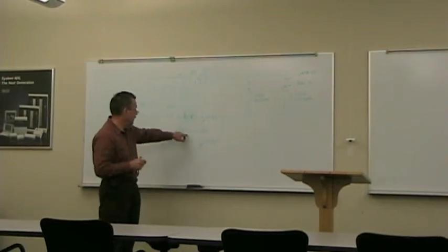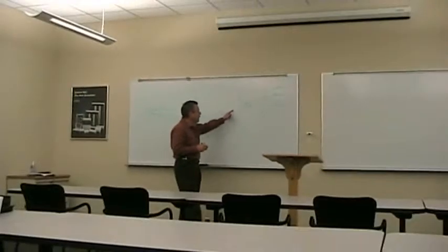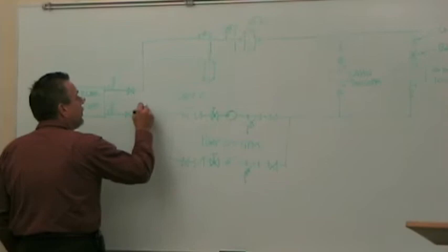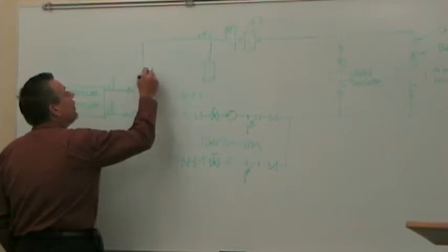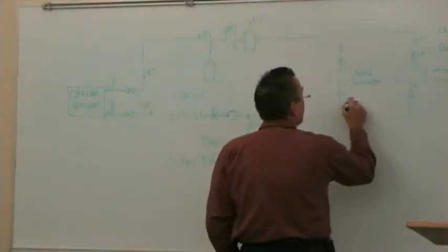Parallel pumps, one's redundant, it's 200 gallons a minute. We have two air handlers at 100 gallons a minute apiece. So, a 4-inch pipe out here, 3-inch pipe here.